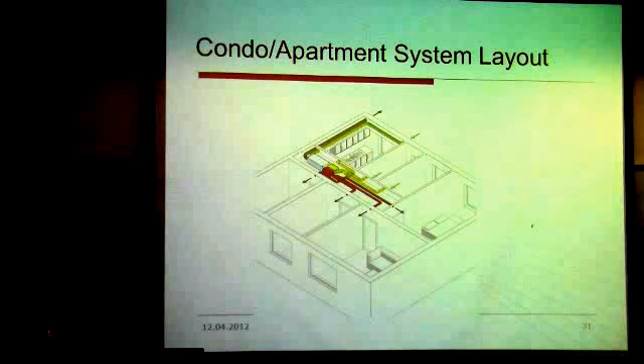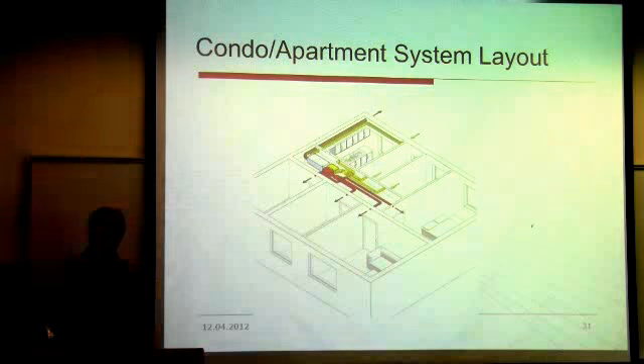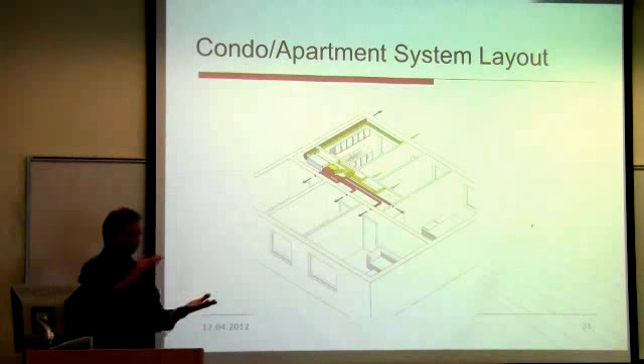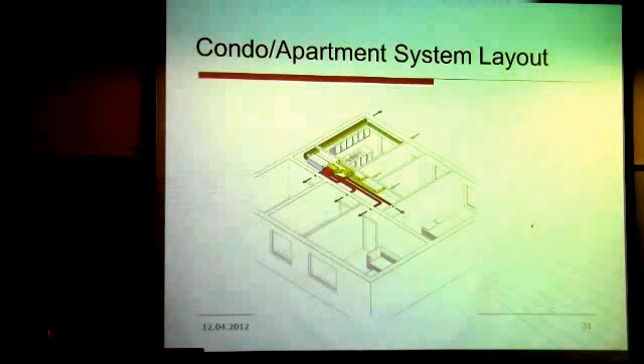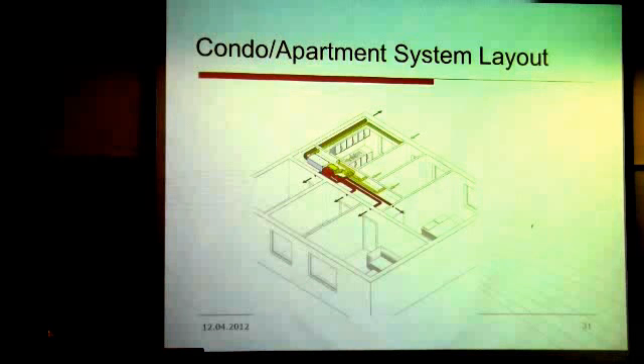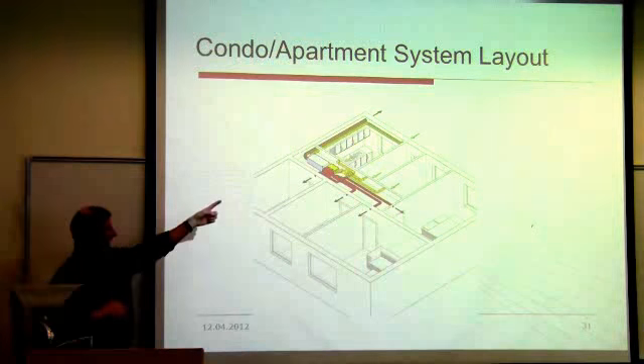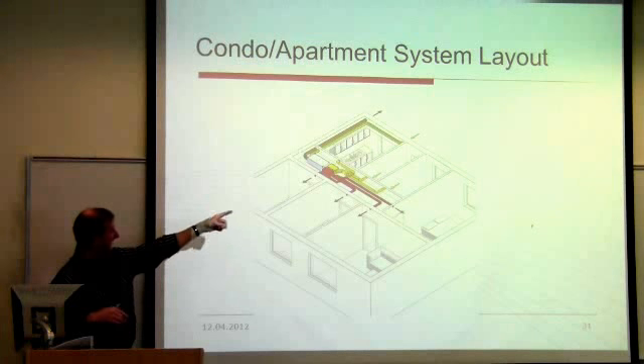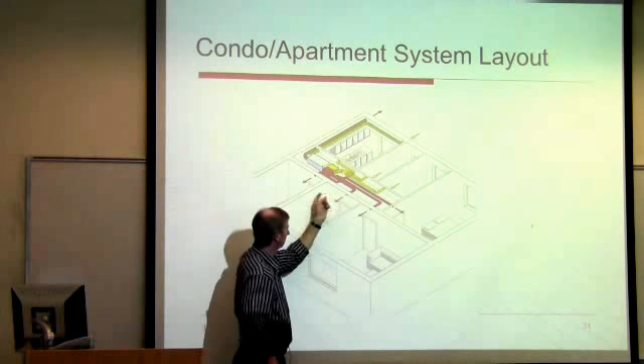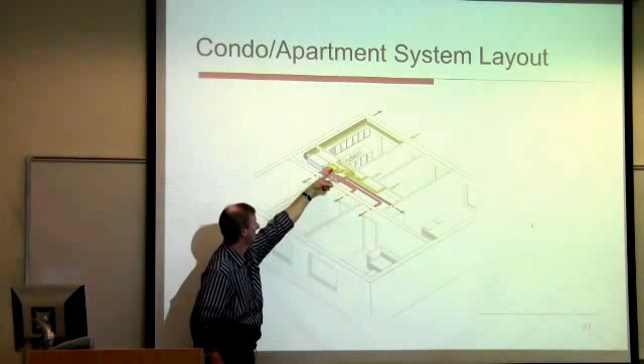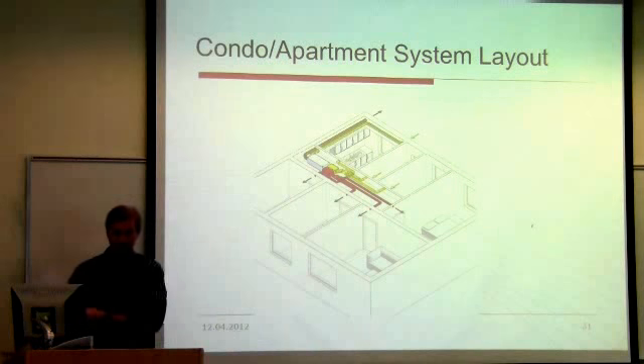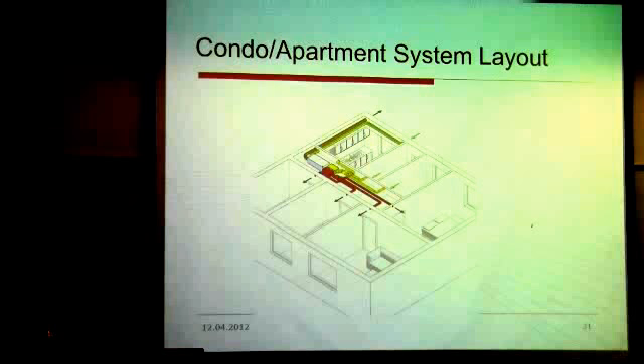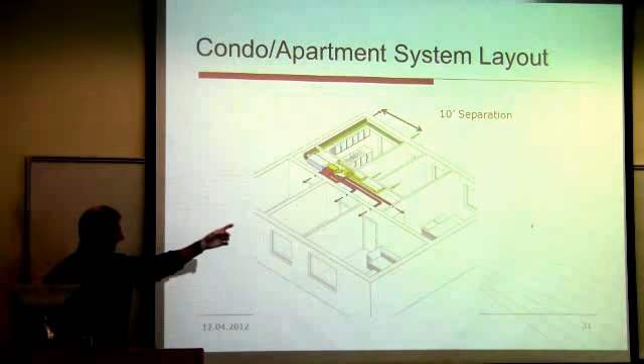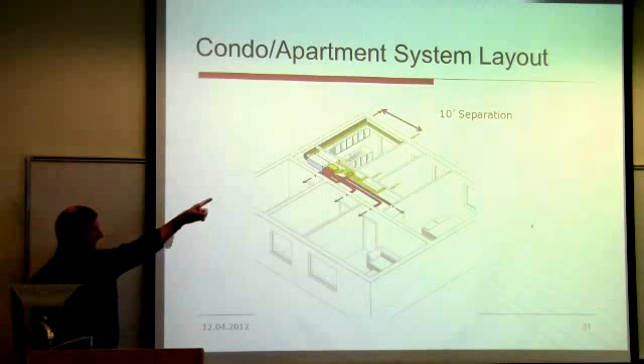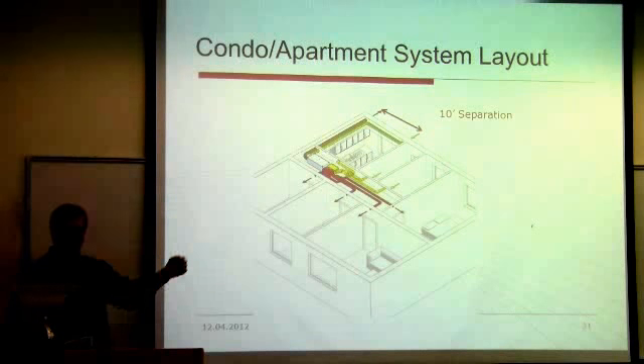If you're in a smaller, compact type of house, they actually built systems that you can just drop, especially in a retrofit, you can just drop maybe the hallway. If the hallway's got some decent height, you can drop the hallway 12 inches or 10 inches. Fit all the system up there, and you can see it go into the bedrooms, living room, and then exhaust out of the kitchen and bathroom. So that's used more in a retrofit application. And then usually most codes, you have to keep 10 feet separation with the intake air and your exhaust air.